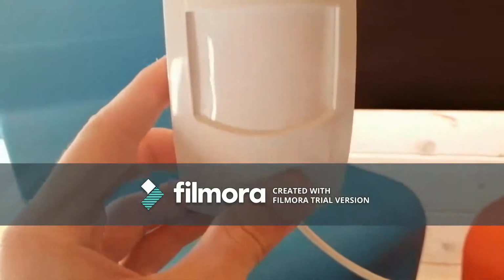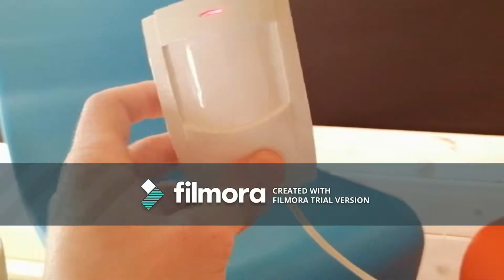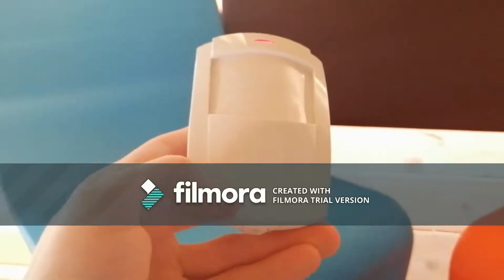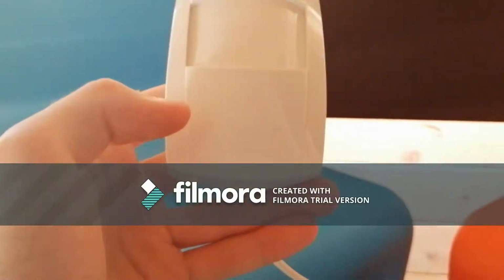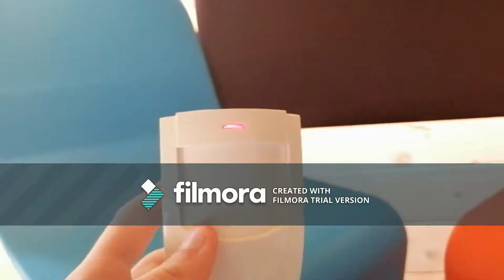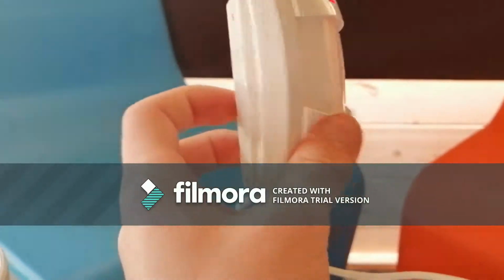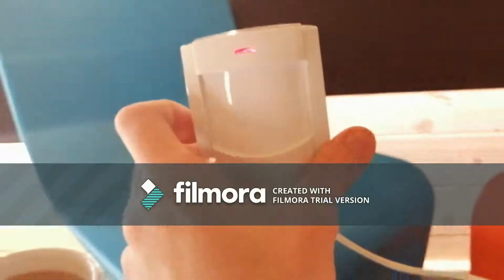And yeah, just fit a new detector, put the wires back like for like, so power, alarm, tamper, and make sure you get positive and negative the right way around, red and black usually. Okay, and it's just a like-for-like replacement.